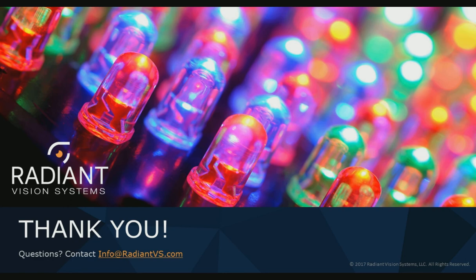And the Y-Series is typically going to be a photometer only. That's a smaller version of our cameras without the moving filter wheel component, and it will either have just a photopic filter in the optical path, or in some cases it'll even have a radiometric filter in the optical path. And it is also possible to measure in radiometric units within the software as well. So basically any of our imaging colorimeter or imaging photometer products will be able to work with the latest renditions of the software.